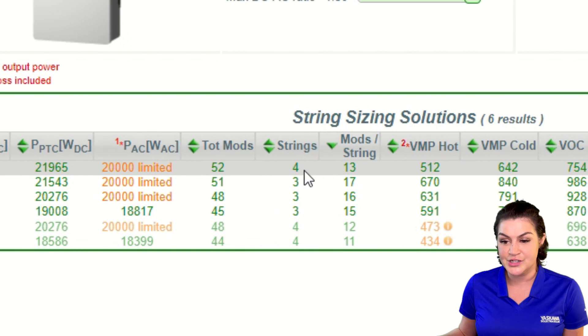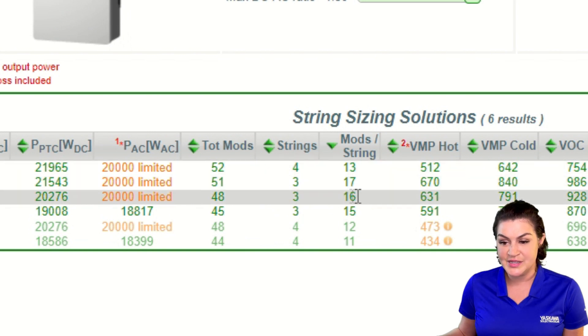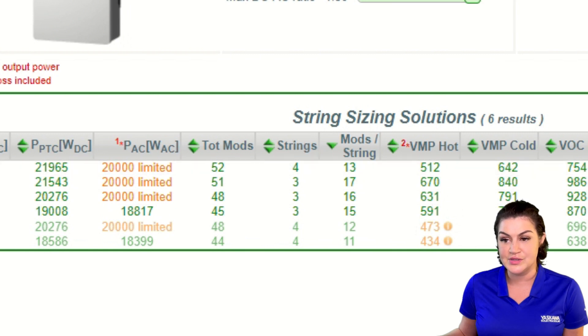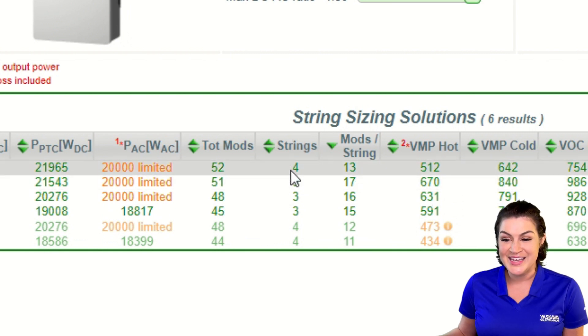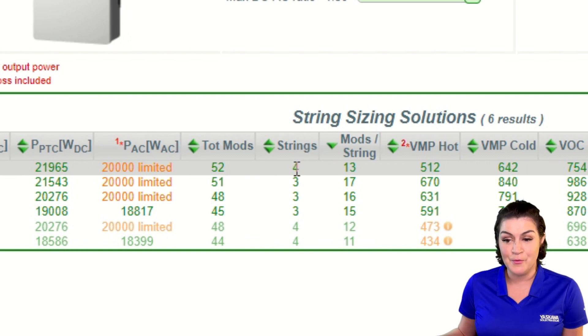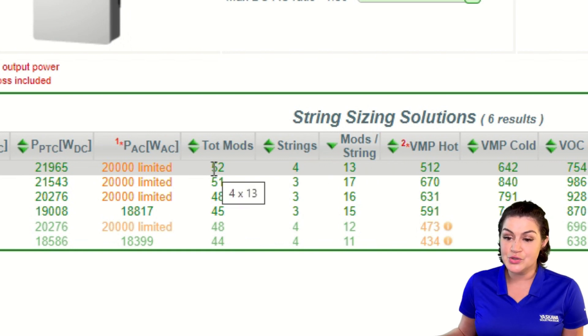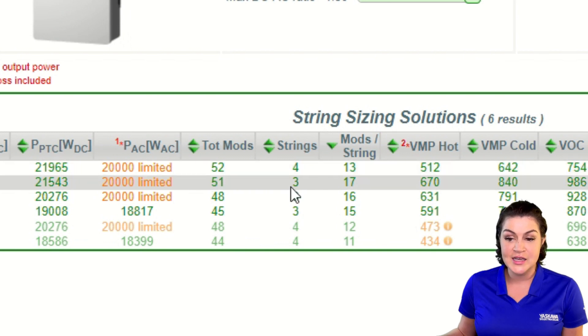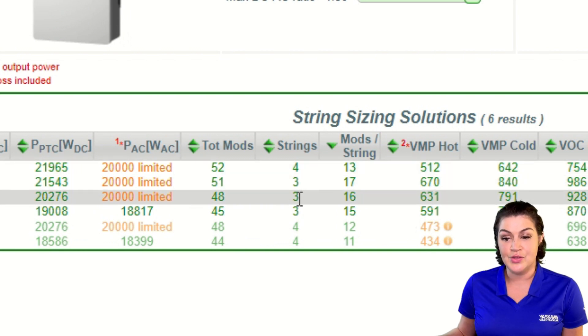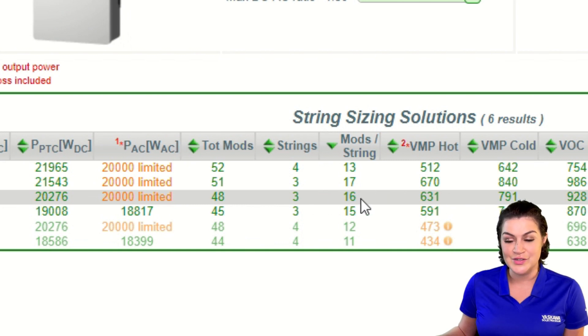I'm going to take a look at these top three. We have a four by 13 configuration, three by 17, and three by 16. We could choose any of these for our individual MPPT zones — we have one of three. So we could do all three MPPT zones at four by 13. But if I have, for example, 151 of these modules, I could do one zone at four by 13, the second zone at three by 17, and the third zone at three by 16, to be able to use all 151 modules.